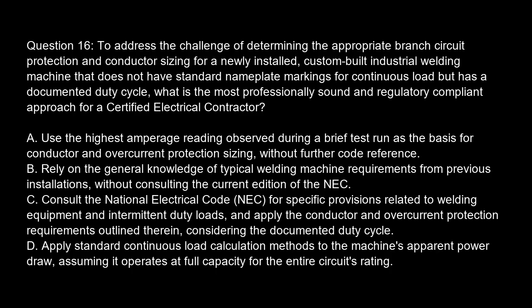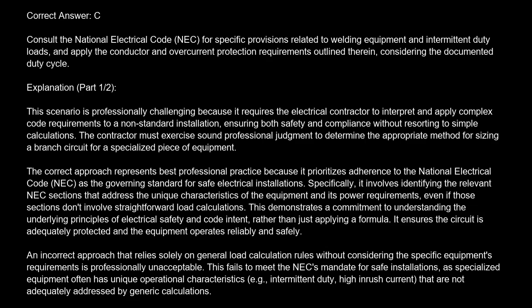Consult the National Electrical Code, NEC, for specific provisions related to welding equipment and intermittent duty loads, and apply the conductor and overcurrent protection requirements outlined therein, considering the documented duty cycle. Option D. Apply standard continuous load calculation methods to the machine's apparent power draw, assuming it operates at full capacity for the entire circuit's rating. The correct answer is C.